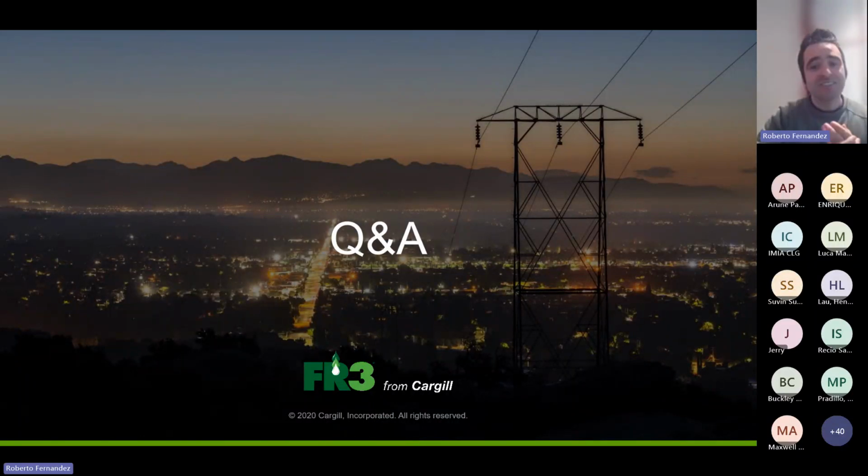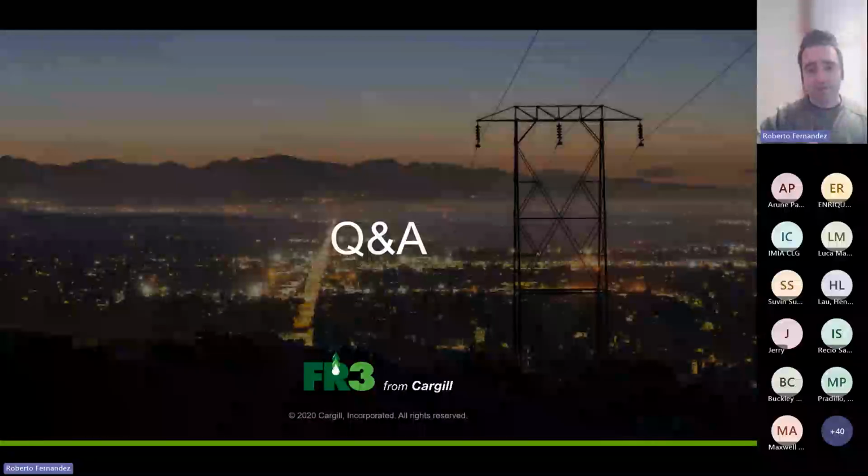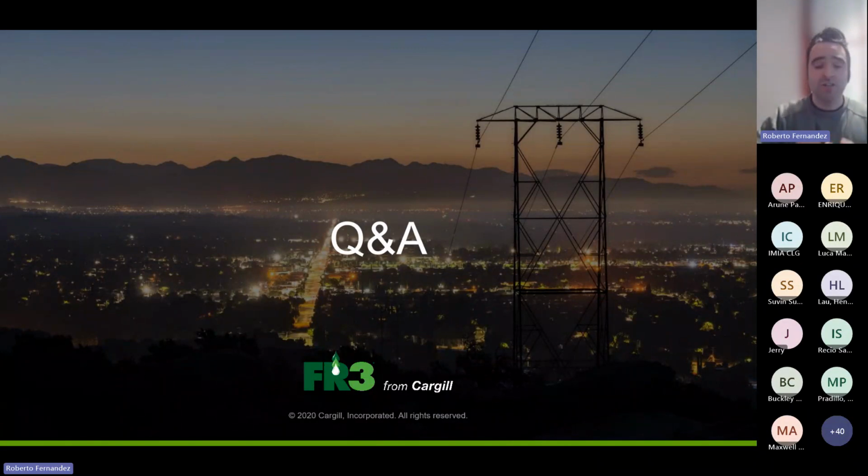Well, not an easy question to answer, but let's say that what's important here is not so much the age of the transformer, but the expected remaining life of the transformer. If there is no other request regarding fire safety and so on, and the idea is to extend the life of the asset with the retrofilling, what is important is the remaining life of the transformer. So if the transformer has 2 or 3 years expected remaining life, it's most likely not a cost-effective solution. We are not going to extend the life another 10 years, okay? So we typically advise the customers that the sooner the better. But of course, if the remaining life is 10, 20 years, 15 years, it's a very good opportunity to make the retrofilling. That's for sure.